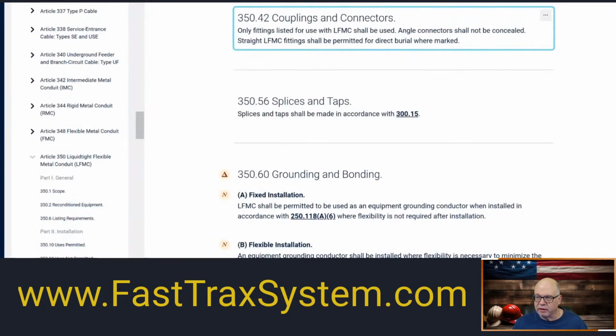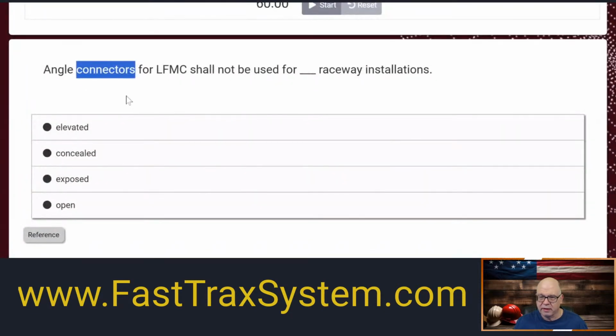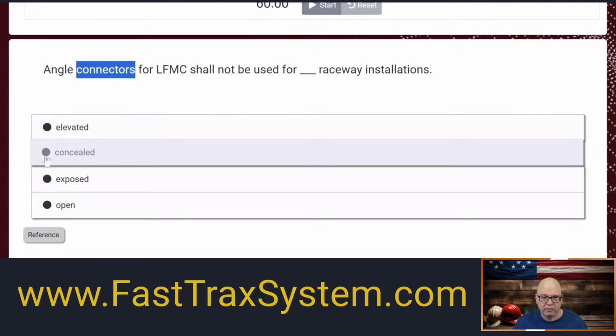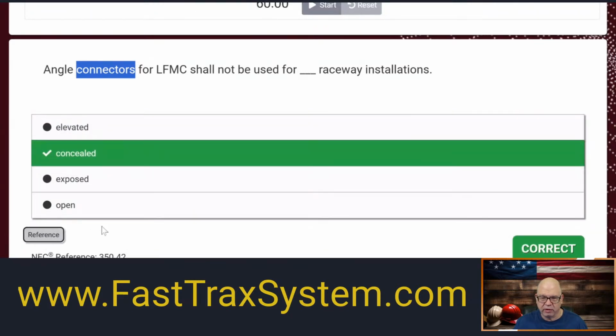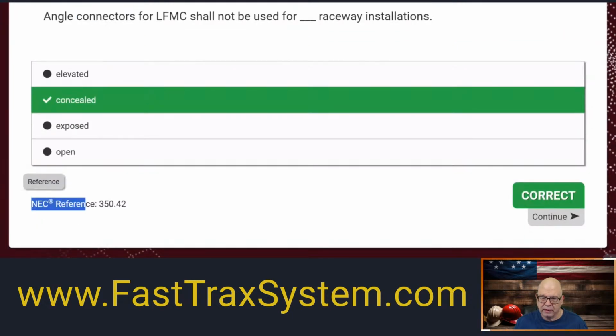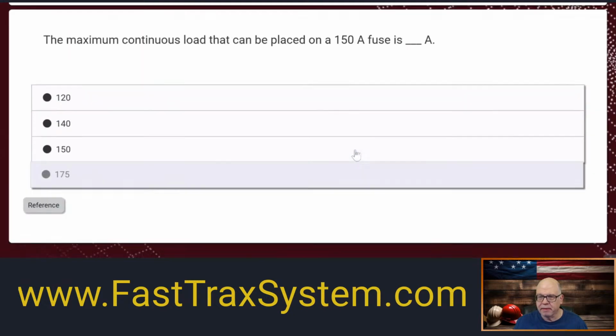For that one here, it says only fittings listed for use with LFMC shall be used. Okay, makes sense, because LFMC is a listed wiring method. And of course, .6 now in the 2023 requires all the fittings to be listed for the wiring method you're using. It says angle connectors shall not be concealed. So it's telling me flat out they're not to be concealed. So we'll go back here, and of our options, right here, concealed. Click it, and there you go. And then we'll give you the code reference right there. NEC 350.42. Okay. All right. What's next?